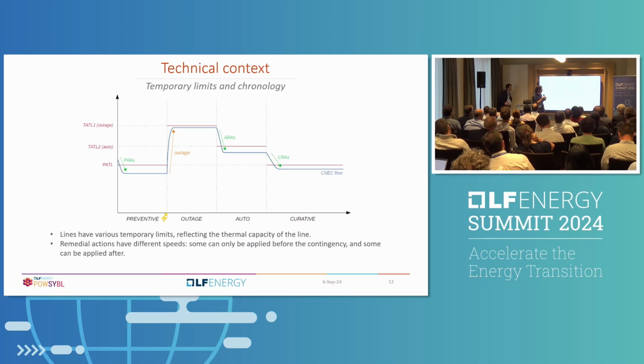Then we have an outage, which happens. And so we first go to the first temporary limit, which is the highest. This is usually around 1 minute to 5 minutes. So maybe it can support 130% of the PATL for 1 to 5 minutes, for instance. Then we will have a second temporary limit, usually 5 to 20 minutes. So it's a new limit, which is a bit lower. And then finally, it has to go back under the permanent limit.